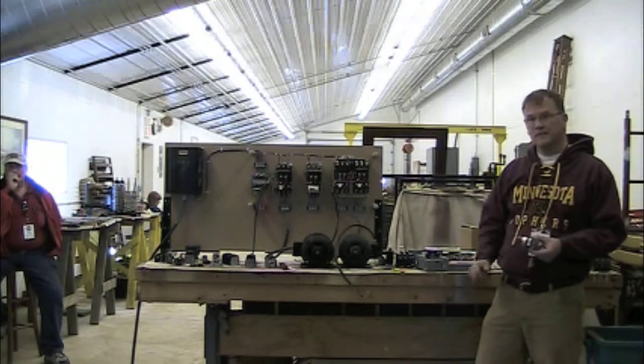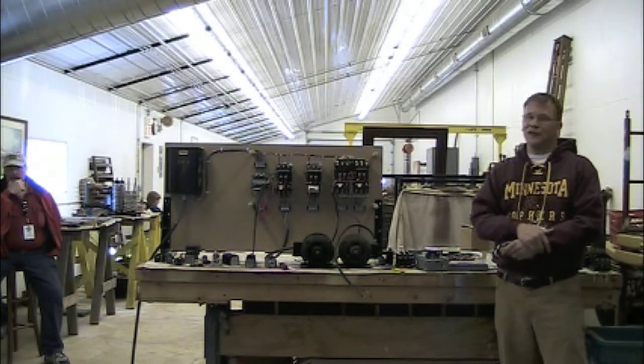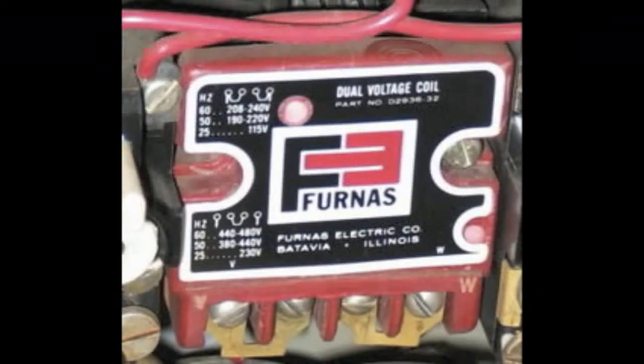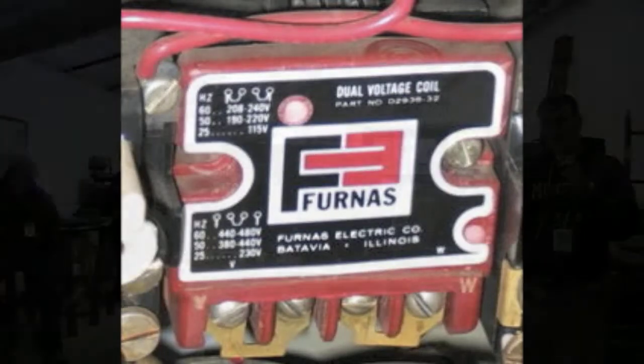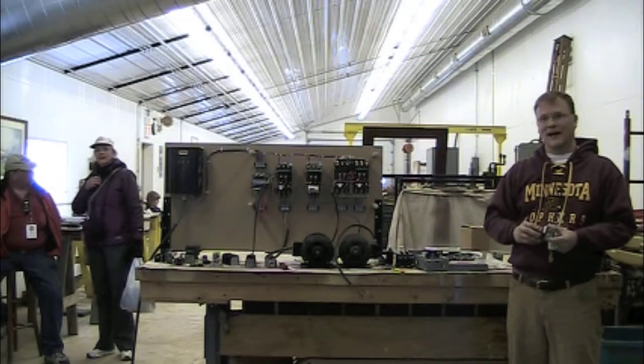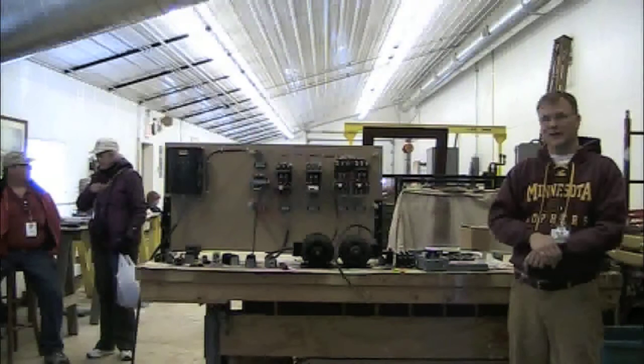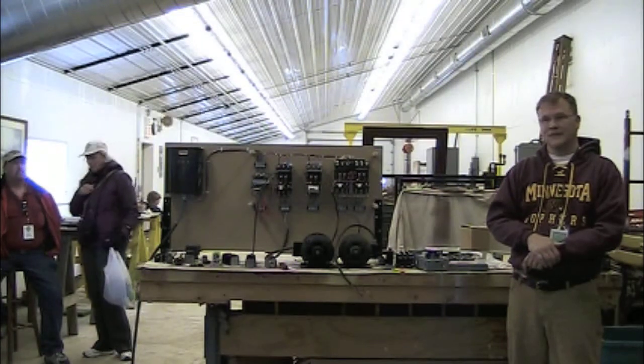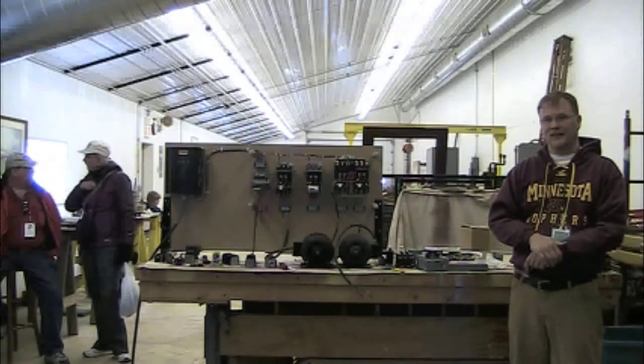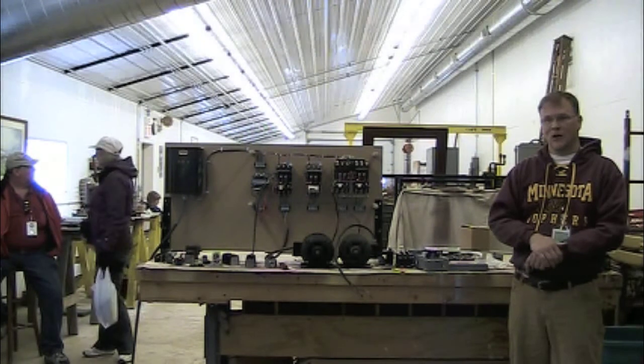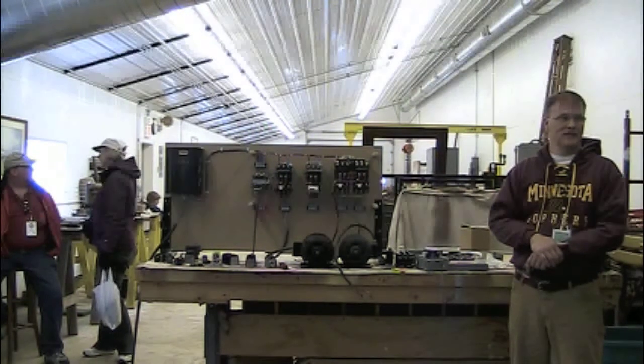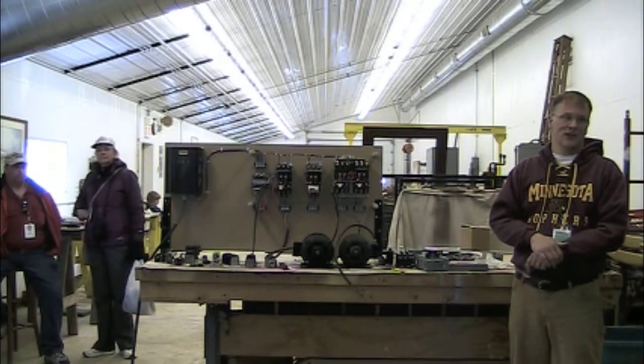Now, most Furnas starters have dual voltage coils. Furnas is kind of an oddball in that they have multi-tapped coils that you can change the voltage on. If you don't know what you're doing, looking at them, you wonder what all this is on here, because there's a lot more you have to be aware of when you wire them. But they're pretty consistent in having multi-voltage coils. Most of the other ones you need to change the coil on.